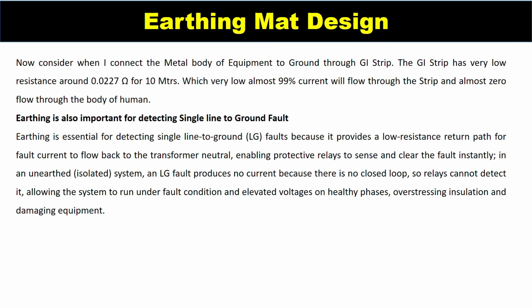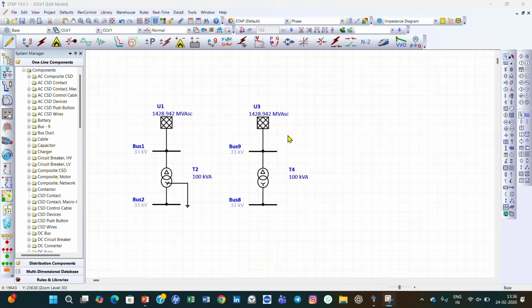So when there is no current, the relays will not sense the fault, and the system is running under fault condition. Another problem is that it also raises the voltage of the other healthy phases. When a fault occurs, the voltage of the other healthy phases increases, which causes overstressing of the insulation and damage to the equipment. I will show this to you on the ETAP. This is my ETAP.